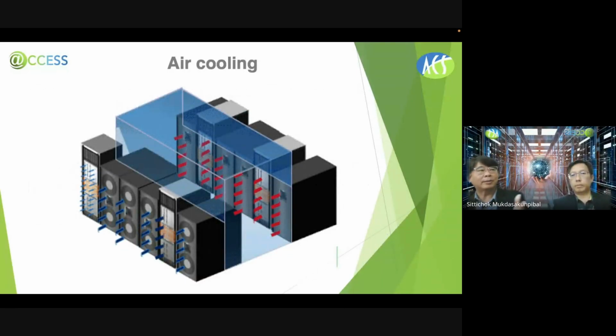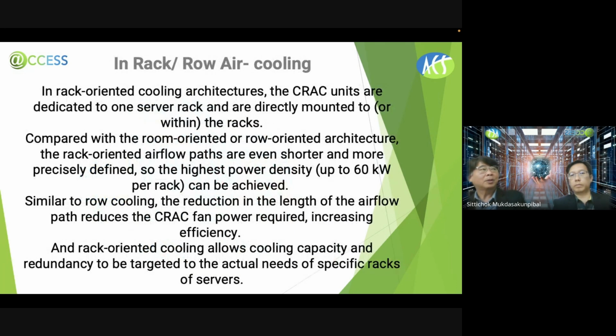So this is one sample of air cooling. I've seen this working, running on AI, NVIDIA CPU as well, and it works pretty well. So that can be something like the in-rack or row air cooling, but then it is specifically designed just for the AI side. You can cover all the way up to 60 kilowatts per rack.